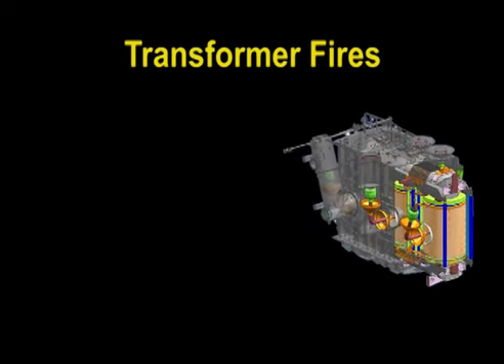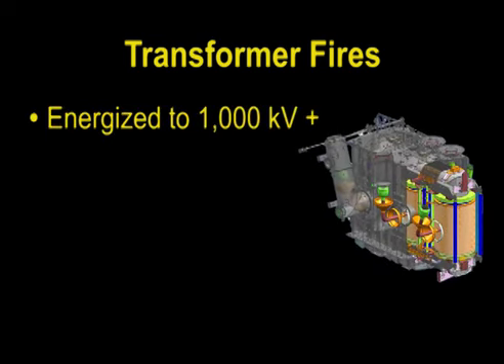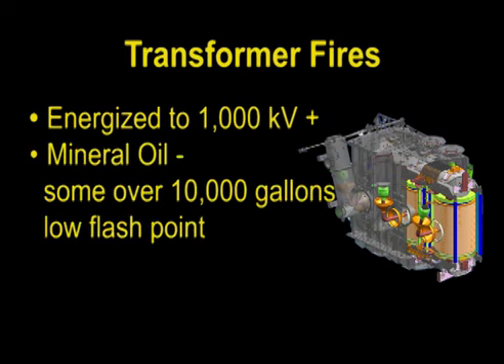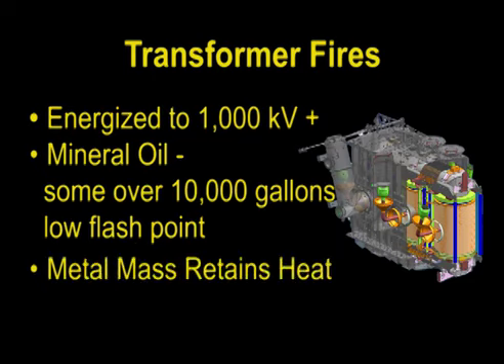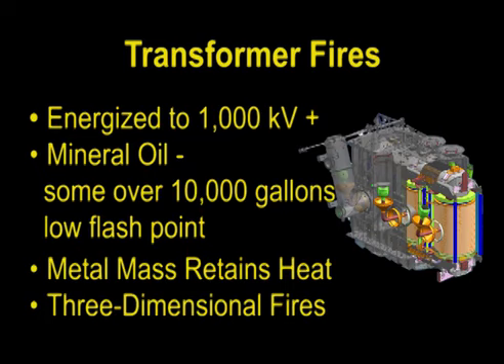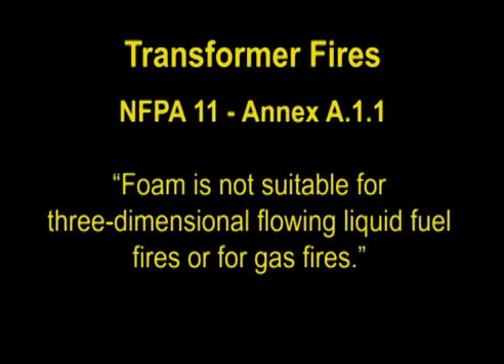Transformer fires are complicated. First, they are energized, some over 1,000 kilovolts, and the power must be removed to prevent electrical feedback to the firefighter. Also, transformers can contain over 10,000 gallons of mineral oil with a flash point around 284 degrees Fahrenheit. During failure, the oil feeds the fire. The large amounts of metal retain the heat above the flash point of the oil. Finally, transformer fires are three-dimensional fires.